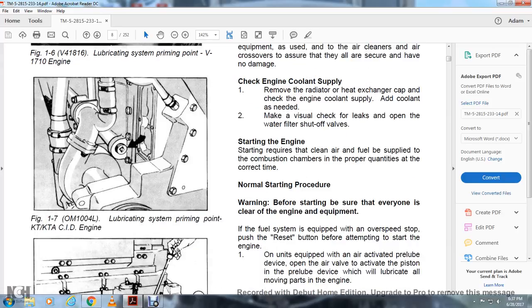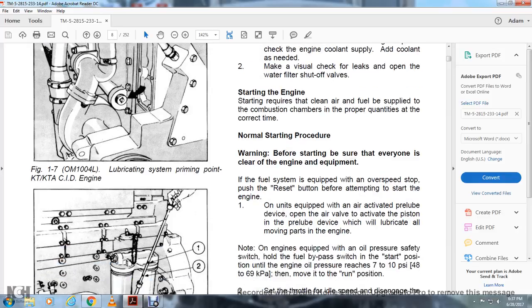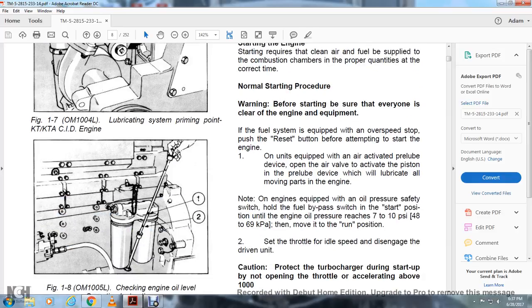Starting the engine. Starting requires clean air and fuel being supplied to the combustion chamber in proper quantity at the correct time. Normal starting procedure. Warning: before starting, be sure that everyone is clear of the engine and equipment. The fuel system is equipped with the overspeed stop. Press the reset button before attempting to start the engine. On units equipped with the air-activated pre-lube device, open the air valve to activate the piston in the pre-lube device, which will lubricate all the moving parts in the engine.